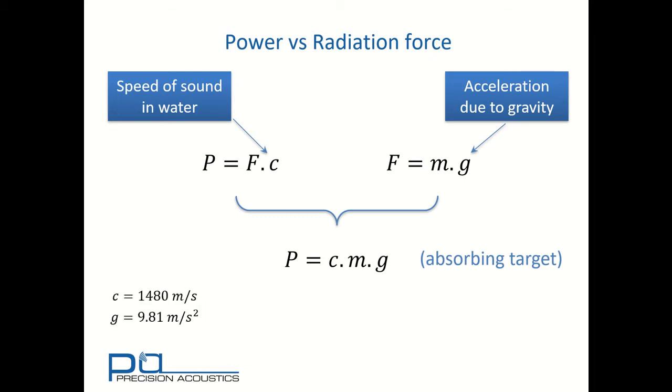For typical values of speed of sound in water of 1480 meters per second and acceleration due to gravity of 9.81 meters per second squared, we find that the conversion factor between effective mass and power is only 68.9 milligrams per watt. Therefore, if we're to measure powers below 10 milliwatts, we need to be able to effectively measure masses below one microgram. This requires highly accurate microbalances.